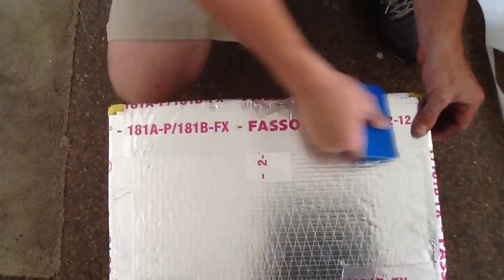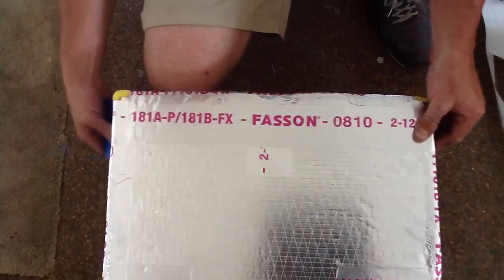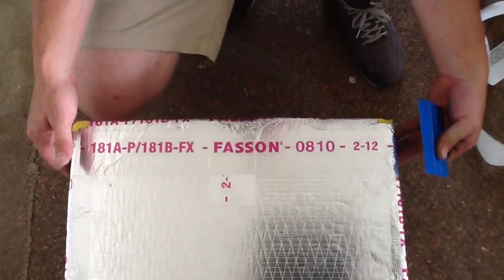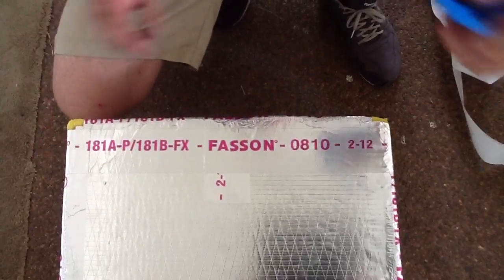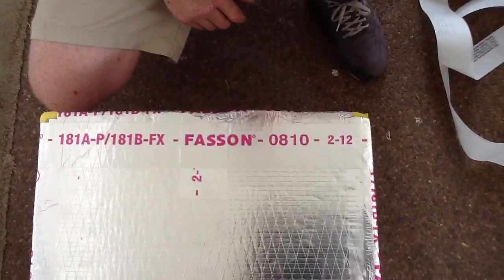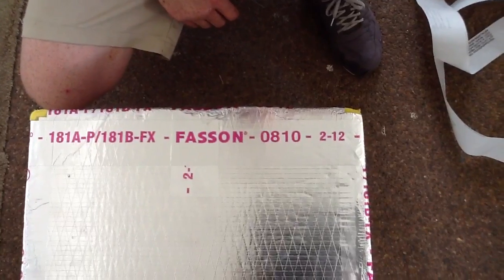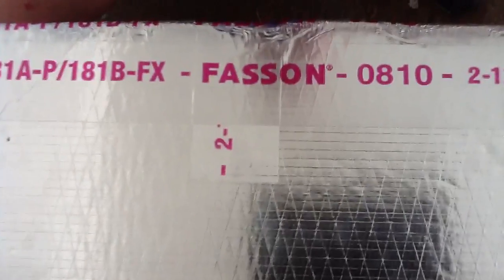Now one thing I want you to see — this is UL181 and the brand is Fasson. One thing I like about this stuff: when you go into a customer's house, it's date-coded 0810212, which means this tape was actually made in February 2012. See how he's got the lines pressed down? This is sealed properly. This is the way it's supposed to be. This is what the manufacturers expect.